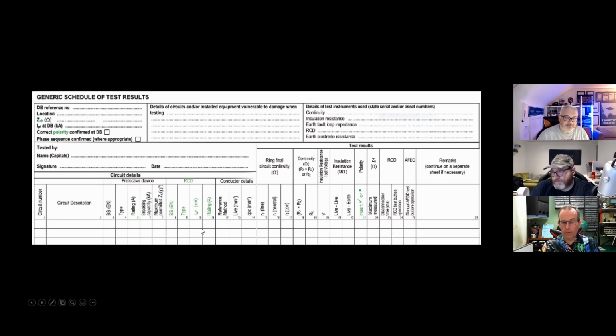Now if you look at the circuit details, they've added a whole new section called RCD - a bit weird, we have then BSEN here, we have type so A, B, F, we have the I delta N rating and the rating in current. We then have conductor details, ring final continuity of conductors, insulation resistance, test voltage.